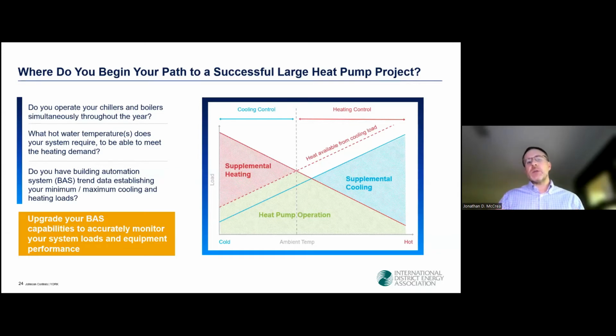And because it'll give you the highest COP and the best payback, what we really want to evaluate here is: is simultaneous heating and cooling a good fit for your system? Can we apply a heat pump in that fashion? So the first question is, of course, do your chillers and boilers operate simultaneously? And assuming the answer is yes, the next question is, does that happen some of the time or is it all of the time? And I would say in many cases for a campus loop or a district energy system, the answer is all of the time, a lot of times.